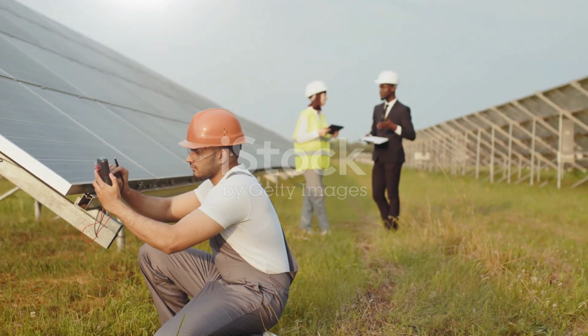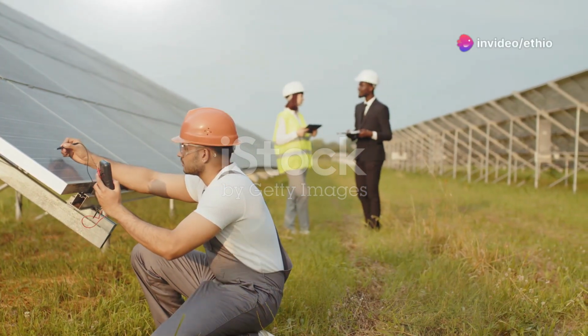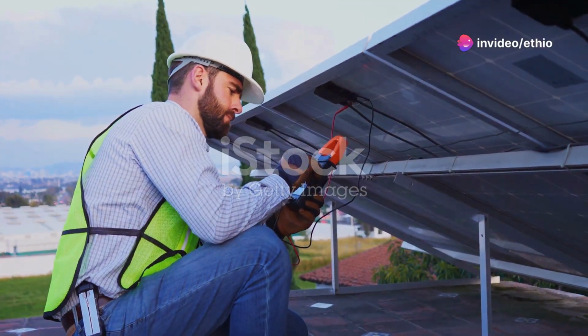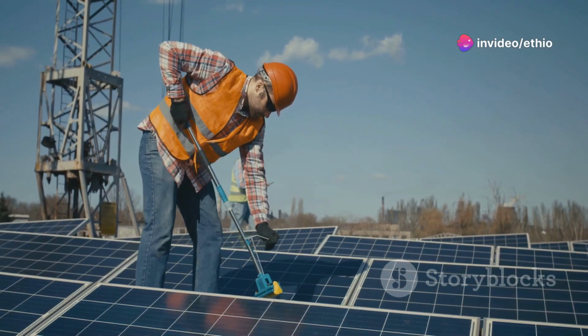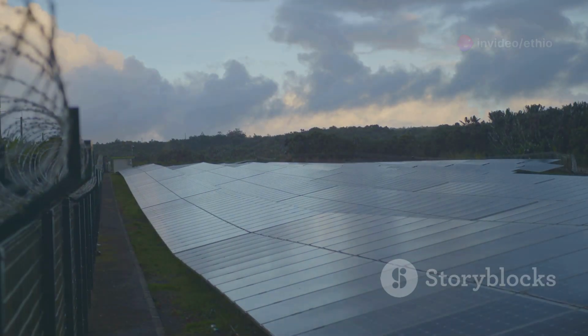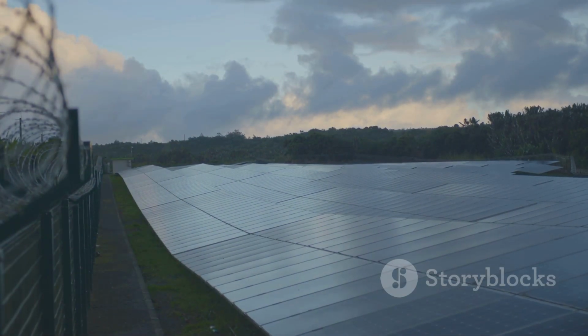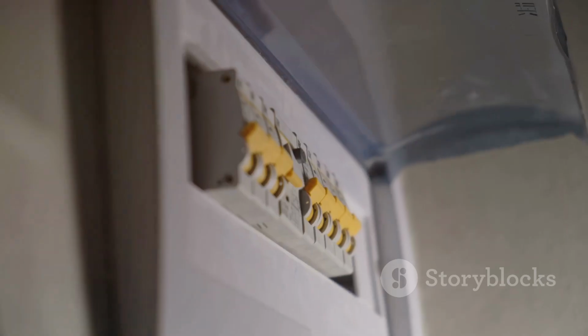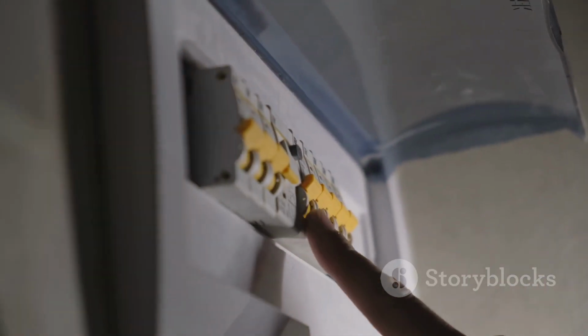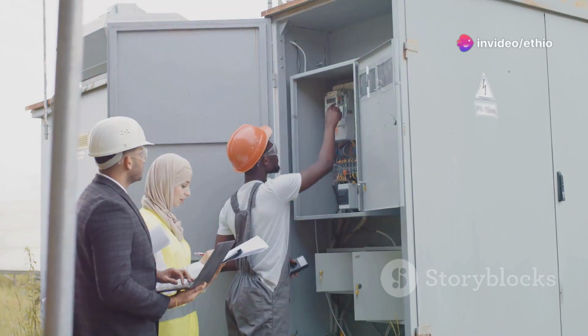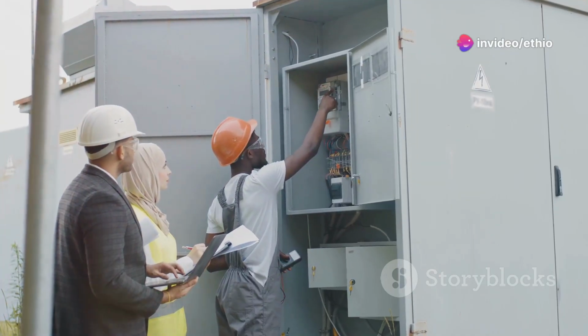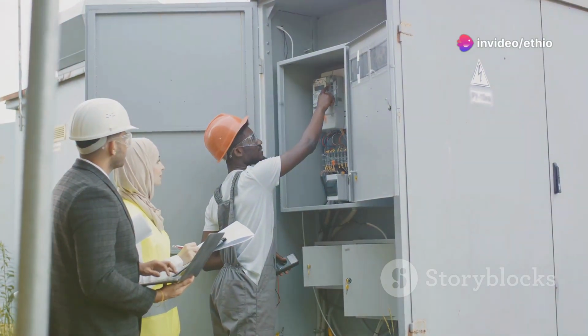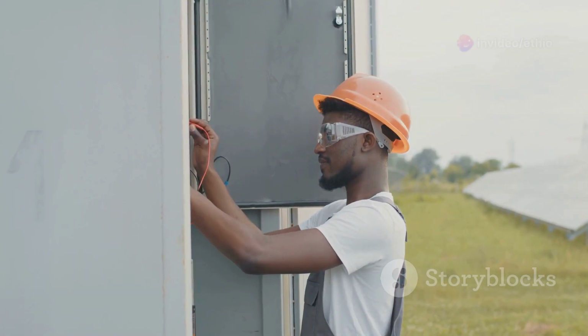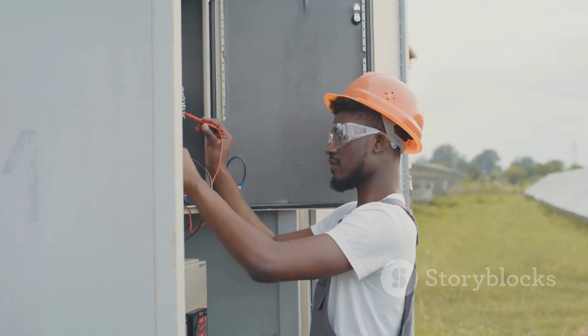Before you touch anything, safety comes first. Solar power systems can be dangerous if you don't take care. Even on cloudy days, solar panels can make enough power to give you a shock. Always turn off the inverter before you open or touch it. Use the main isolator switch, usually near the inverter or your electrical panel. Wait a few minutes after switching off to let any stored power drain away.